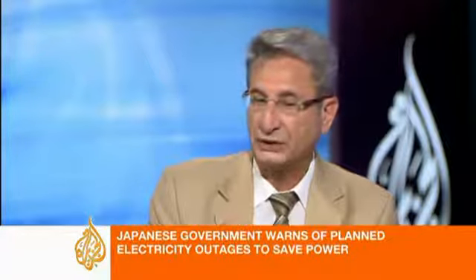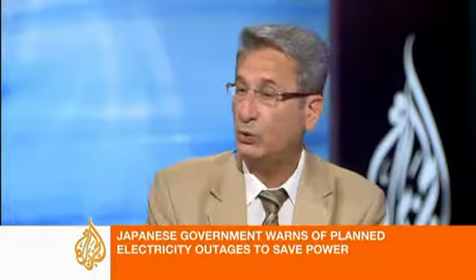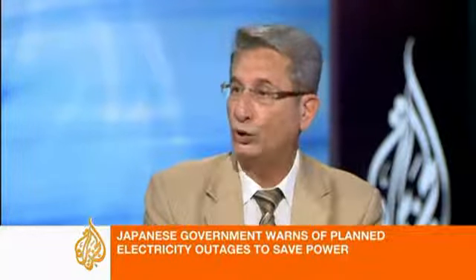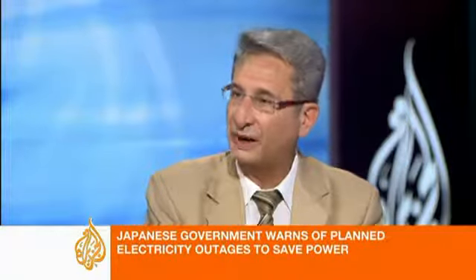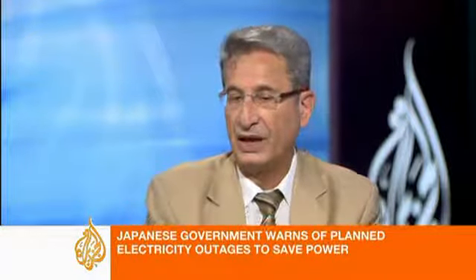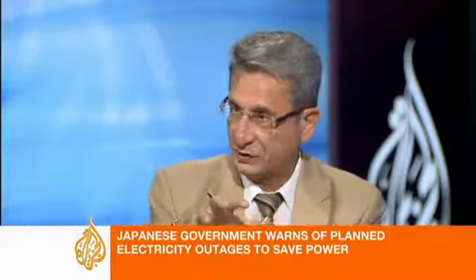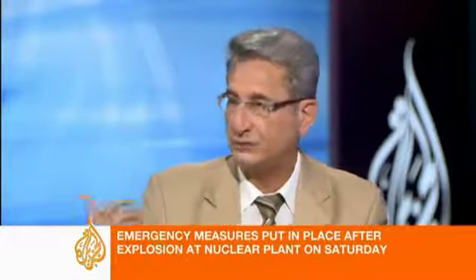Yes, as soon as the earthquake occurred, there were, by the way, 6 reactors at that site. 3 were in service, and 3 were not running. Now they immediately shut down, and the diesel generators started pumping in the cooling water, but less than an hour later the tsunami hit, and it disabled the backup generators, and that's where the big problem occurred. The water cooling stopped flowing to the reactors, and then because of the very high heat, hydrogen develops inside the container building, the building which houses the core of the reactor. And that's what happened in Unit 1. It exploded. And then Unit 3 is probably going to explode also.